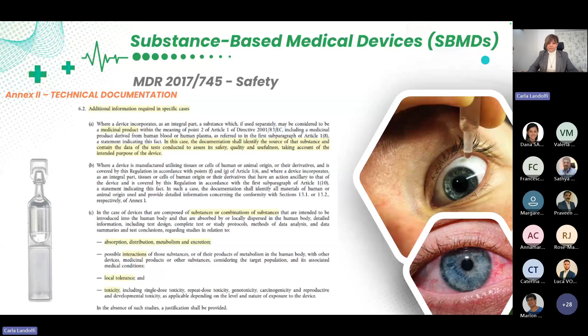Even for ophthalmic medical devices, we must take into account systemic acute and repeated dose toxicity as well as genotoxicity. This requirement applies to all device classes and the evaluation must follow ISO 10993-17, ensuring that the patient's exposure always remains below any toxicological level of concern.